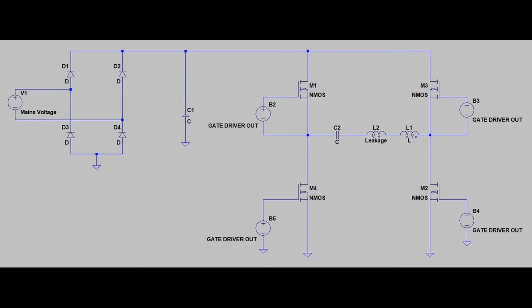In order to invert the DC voltage generated by the rectifier, pairs of diagonally connected switches open simultaneously to draw current through the primary of the transformer, meaning that MOSFETs M1 and M2 open to draw current in one direction through the primary, and then after a period of time, M3 and M4 open up in order to draw current in the other direction. The simplicity of this design allows for quick implementation.